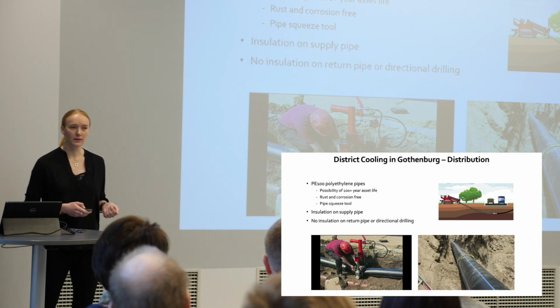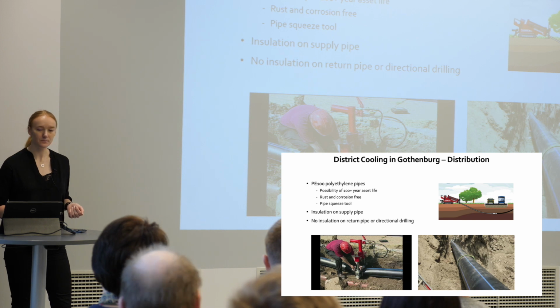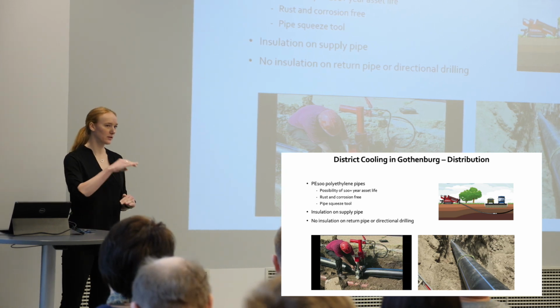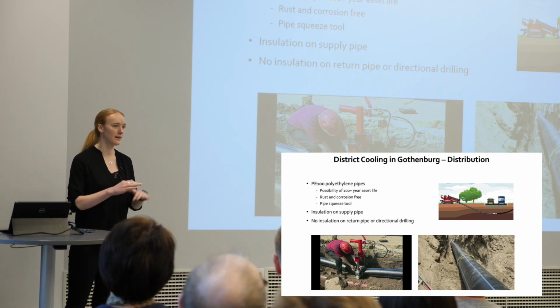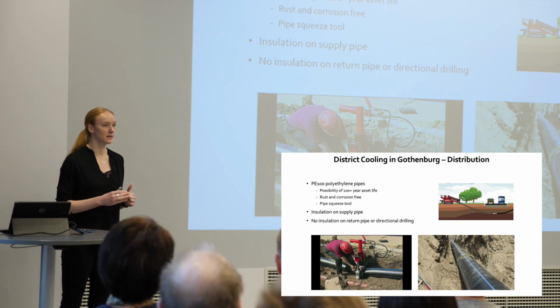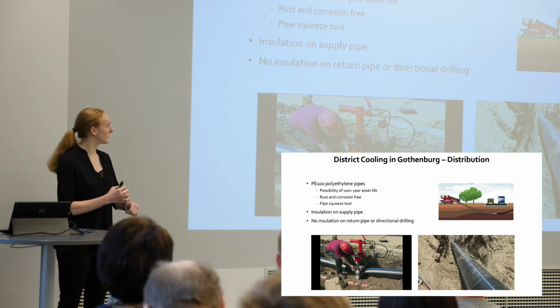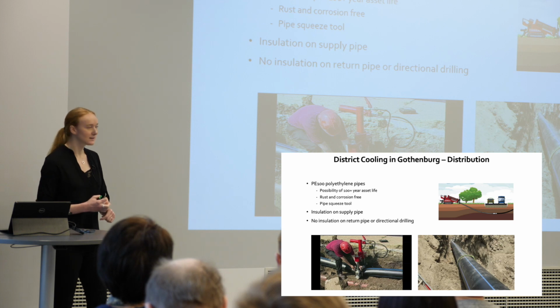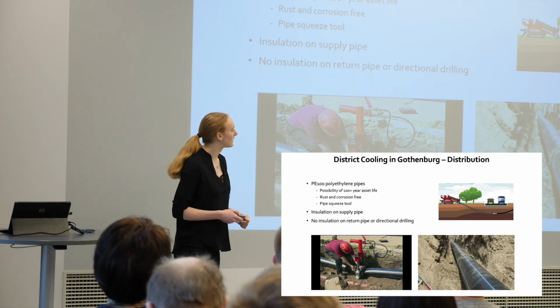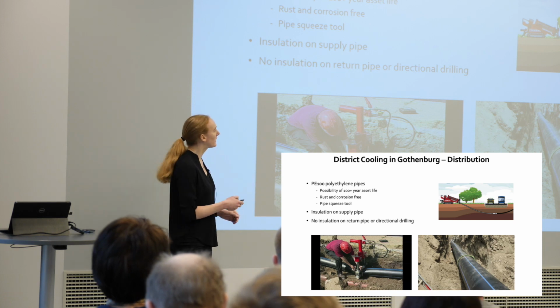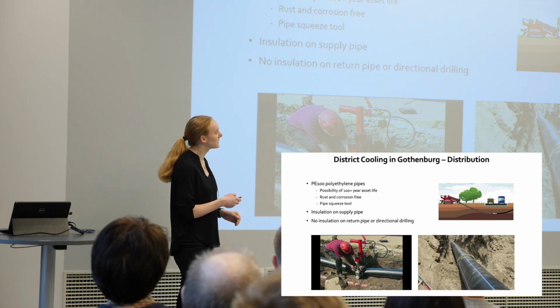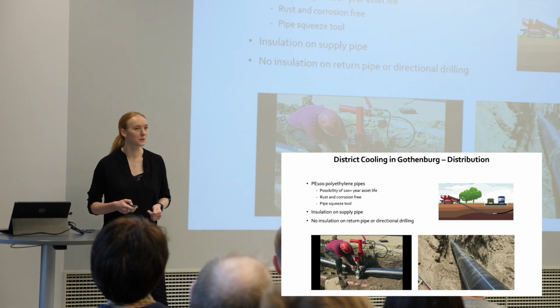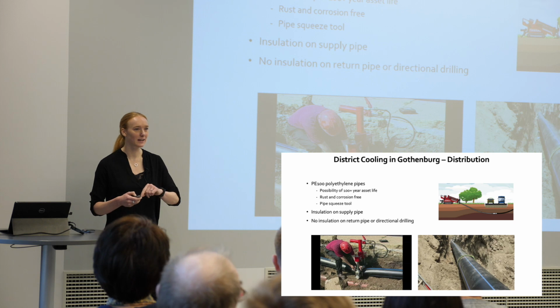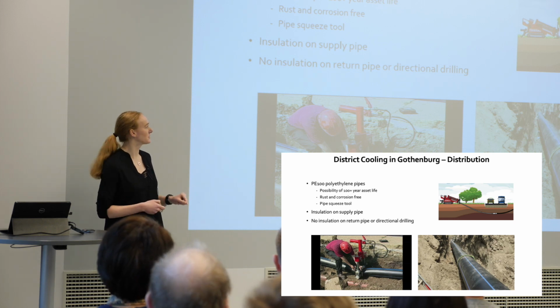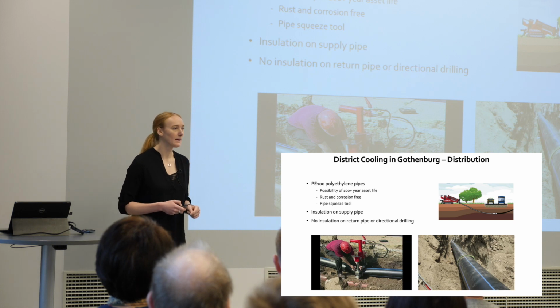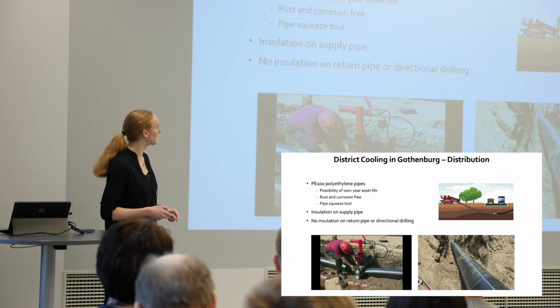In Gothenburg, we only insulate the supply pipe, because when the pipes are located quite close to the surface, in the city where you have a lot of concrete and asphalt, it gets quite warm on the surface, which actually heats up the supply water. So the supply pipes are insulated, but the return pipes are not. Neither supply nor return are insulated when we have to do directional drilling, which means you have to push the pipes through the ground, such as now when we're connecting the two networks and they're using directional drilling underneath the river to go through the ground. So no insulation on those pipes.